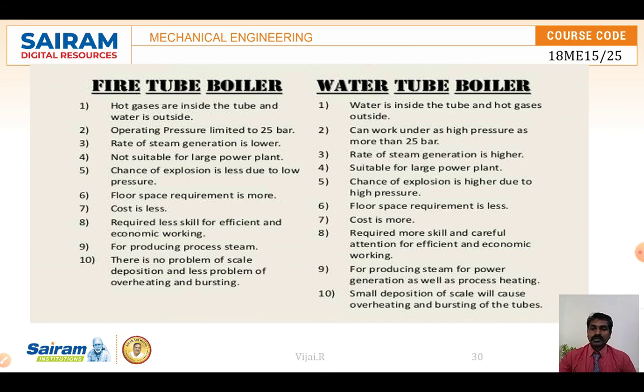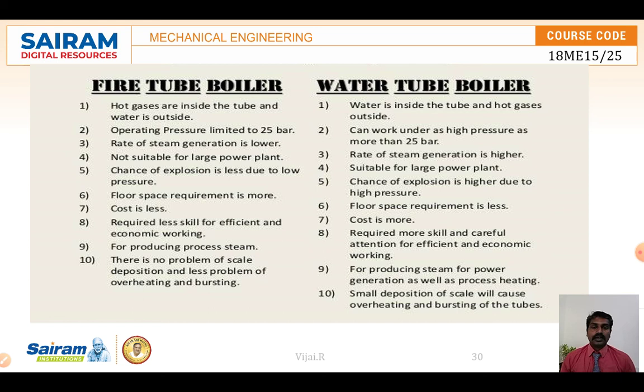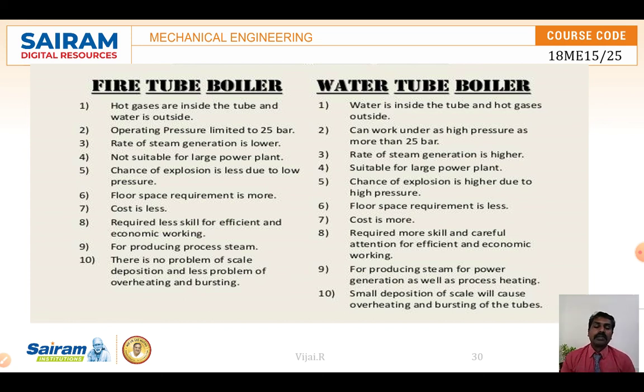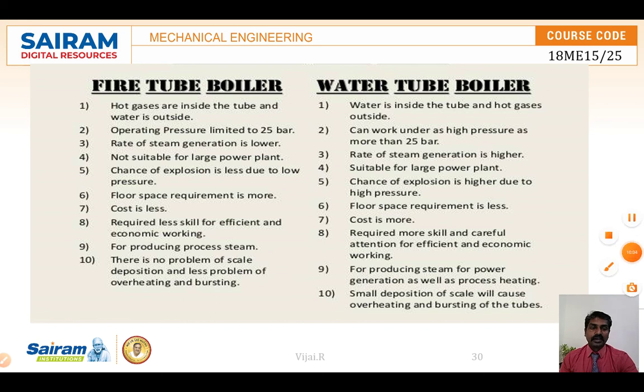Fire tube boilers require less skilled workers and have no problem of scale deposition because water fills the entire drum. In water tube boilers, water passes through small pipes, making scale settlement inside the tubes a significant possibility over time — this is one important drawback. More skilled workers are needed for water tube boilers. Next we will see boiler mountings and accessories.